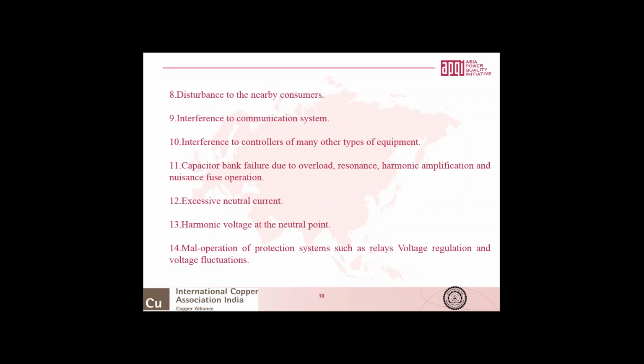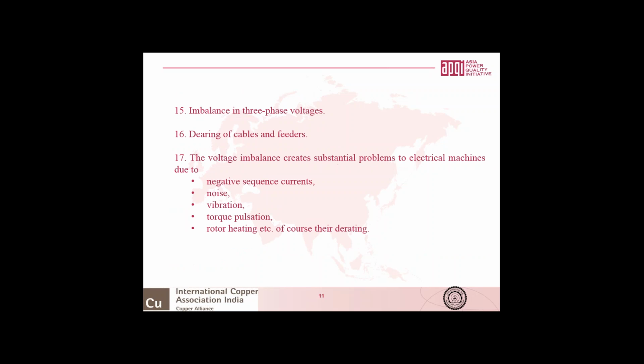To continue, the disturbance to nearby consumers, interference to the communication system, interference to the controllers of many other types of equipment, capacitor bank failure due to overload, resonance, harmonic amplification, and nuisance fuse operation, excessive neutral current, harmonic voltage at the neutral point, mal-operation of protection systems such as relay, voltage regulation, and voltage fluctuations. Imbalance in three-phase voltage, derating of cables and feeders.